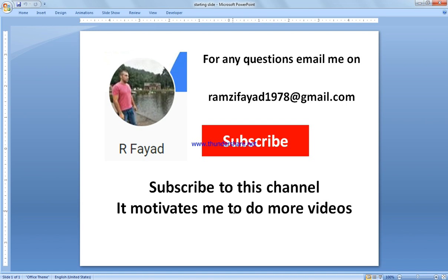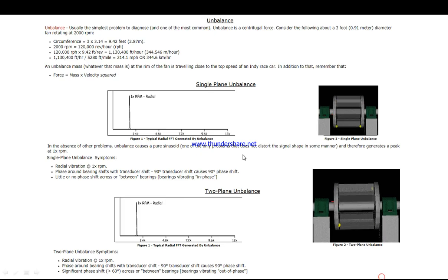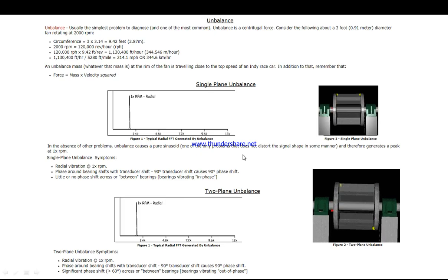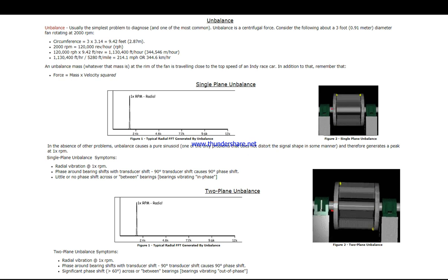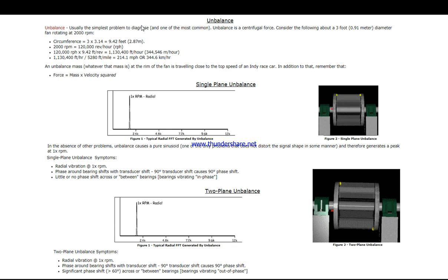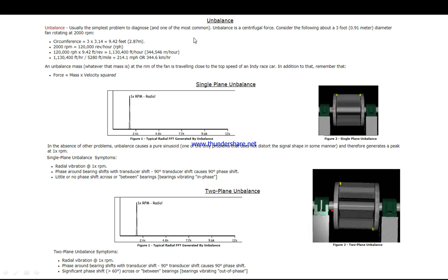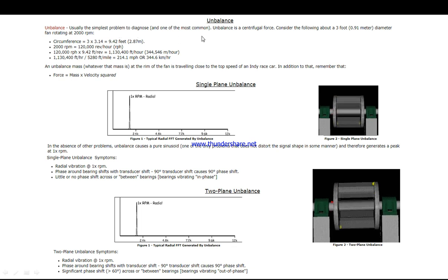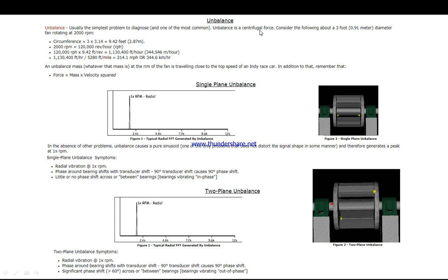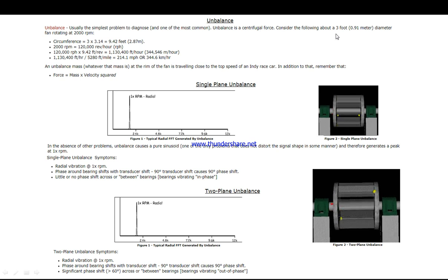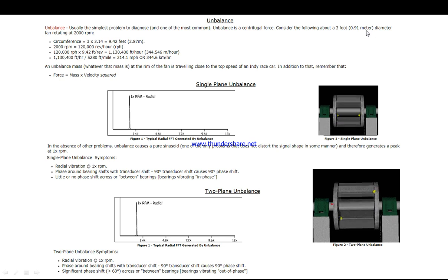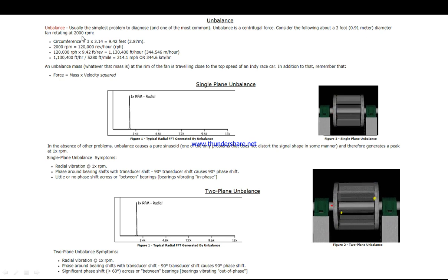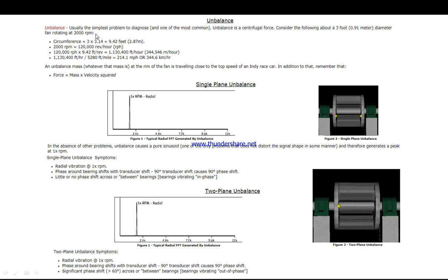Okay, so we're going to consider how to do unbalance spectrum interpretation. To start with, unbalance is usually the simplest problem to diagnose and one of the most common. It's a centrifugal force. Consider the following example: if we have a 0.91 meter diameter fan rotating at 2000 RPM (rotations per minute).